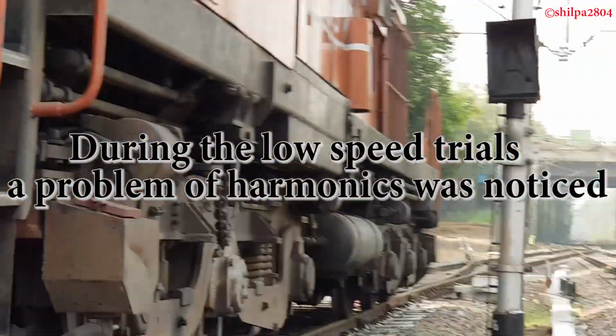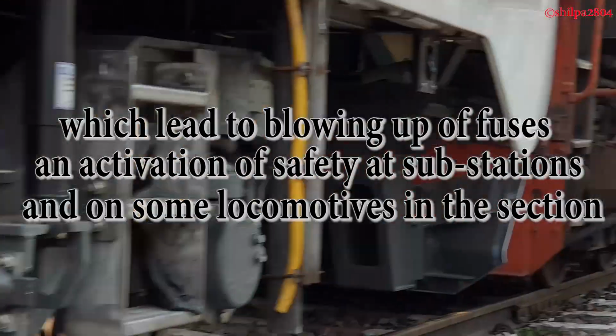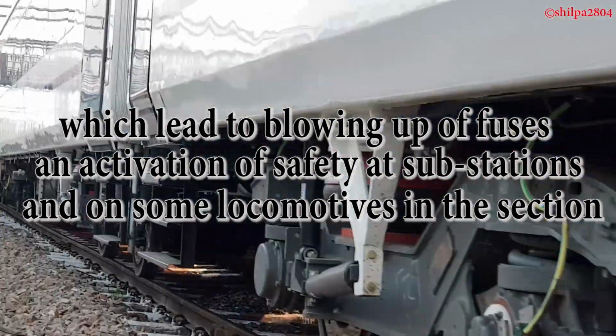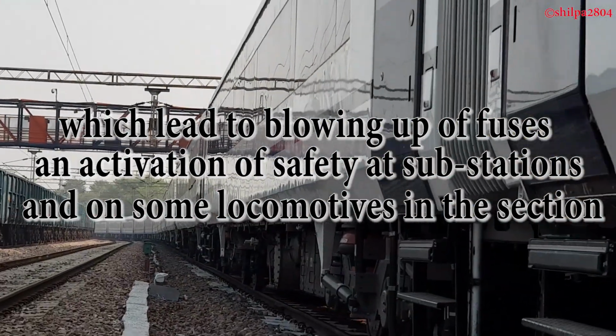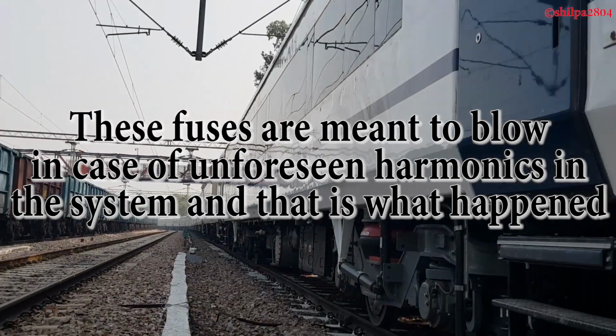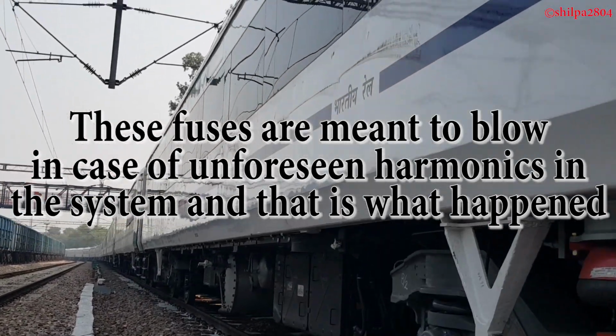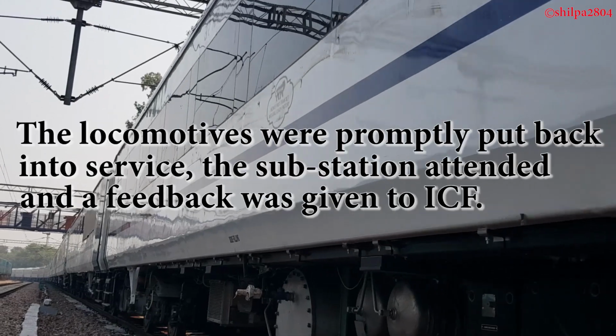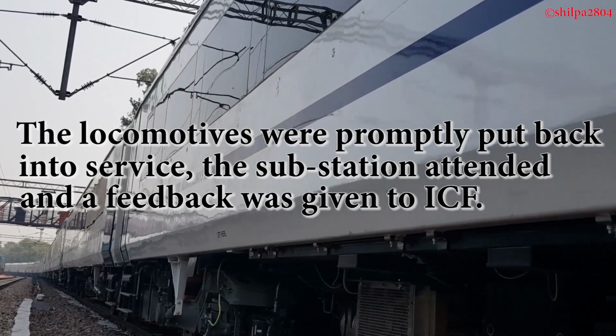During the low speed trial, a problem of harmonics was noted, which led to blowing of fuses and activation of safety at the substation and on some locomotives in the section. These fuses are meant to blow in the case of unforeseen harmonics in the system, and that is what happened. The locomotives were promptly put back into service.